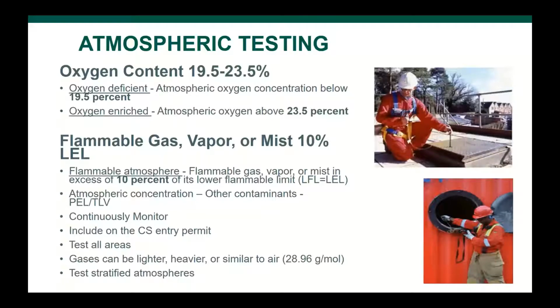You have to test all areas. Remember what we talked about in the behavior of gases? Some are lighter, others are heavier, others close to air. So make sure that you're not only testing the entry point of the confined space. You have to know the internal configuration and take into consideration how the potential gases inside of the space can be behaving, and make sure that you test all the stratified atmospheres.